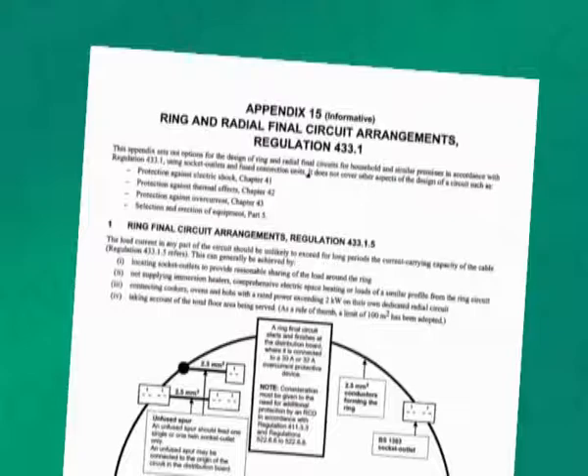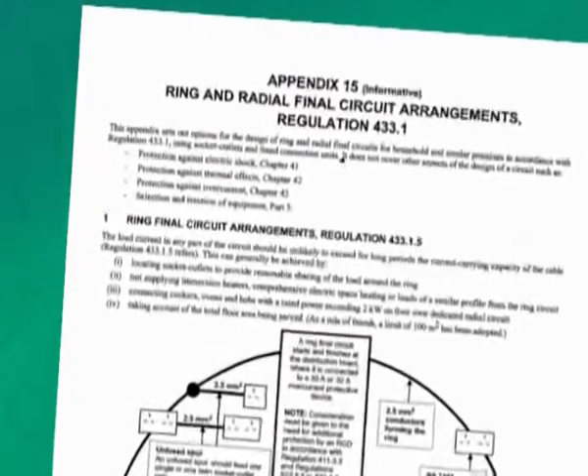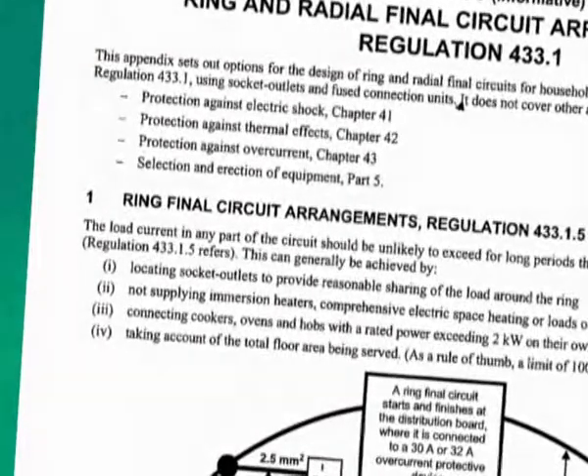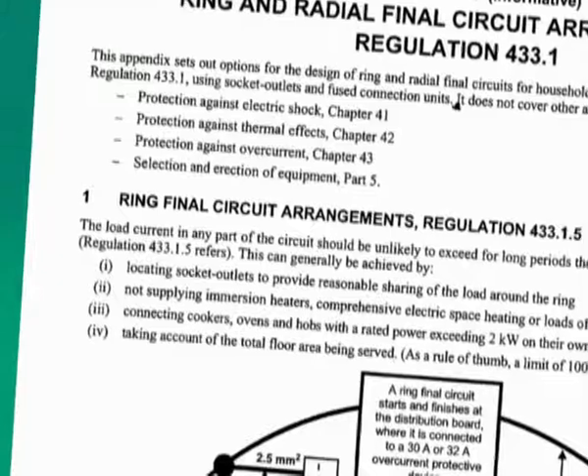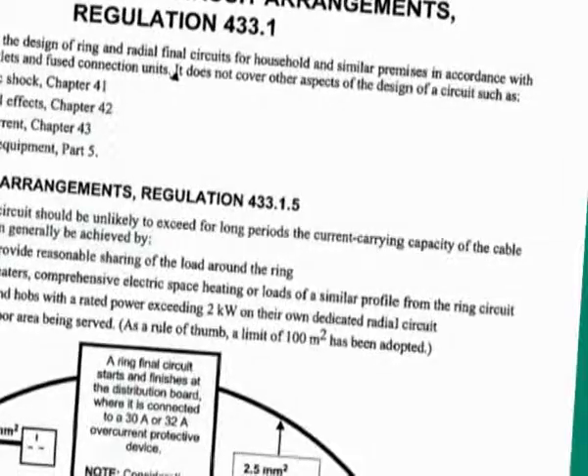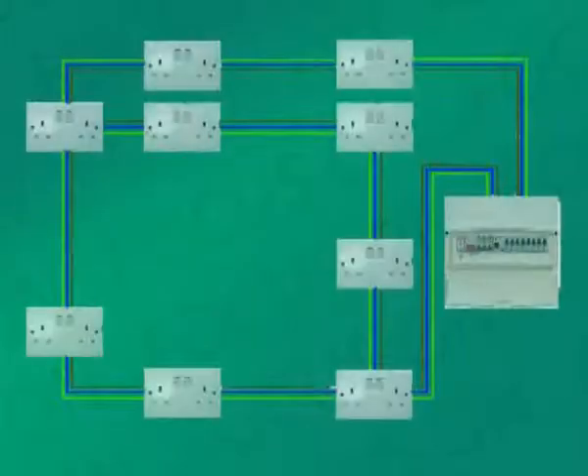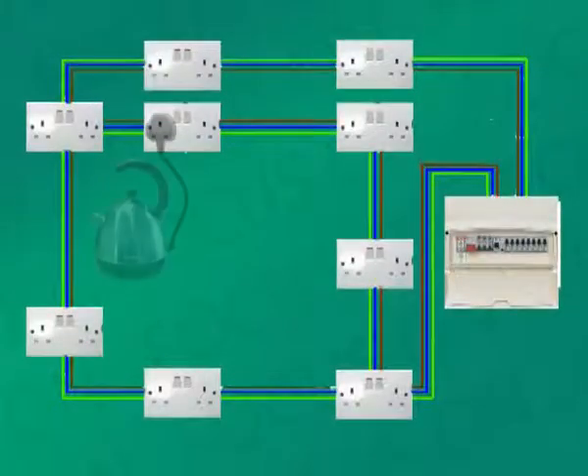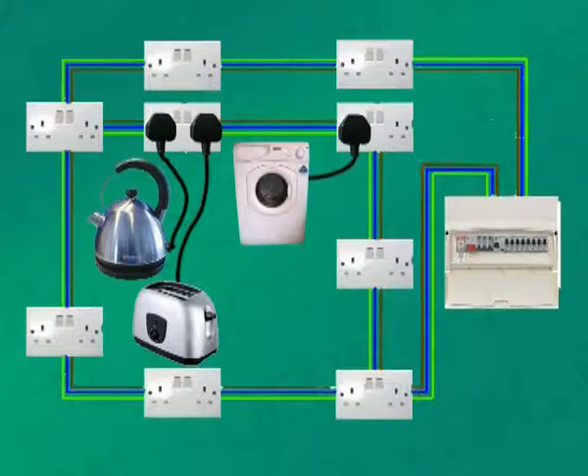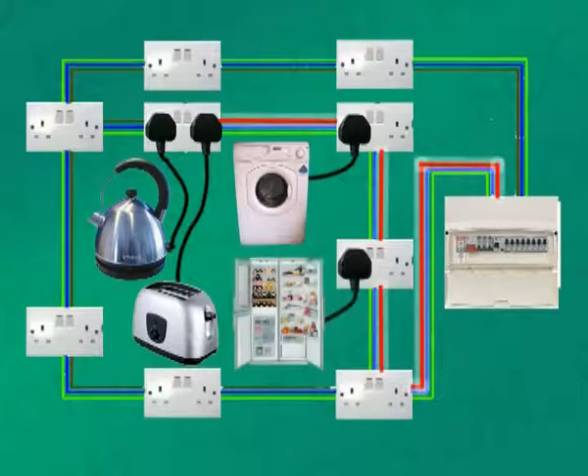You won't see bridges and interconnections ruled out specifically in the regulations. But the requirements of Regulation 433.1.5 need to be met. One of these is that the load current in any part of the circuit is unlikely to exceed for long periods the current carrying capacity of the cable. It's quite possible, in a poorly installed ring circuit with bridges or interconnections, that multiple heavy loads could cause an increased current on specific parts of the circuit. So bridges and interconnections should be avoided.